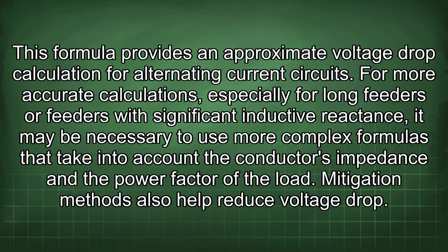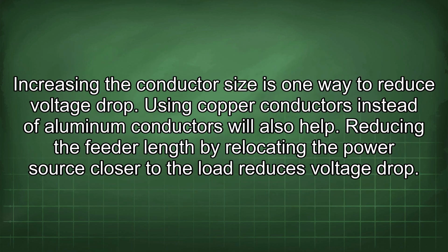For more accurate calculations, especially for long feeders or feeders with significant inductive reactance, it may be necessary to use more complex formulas that take into account the conductor's impedance and the power factor of the load. Mitigation methods also help reduce voltage drop. Increasing the conductor size is one way to reduce voltage drop. Using copper conductors instead of aluminum conductors will also help.